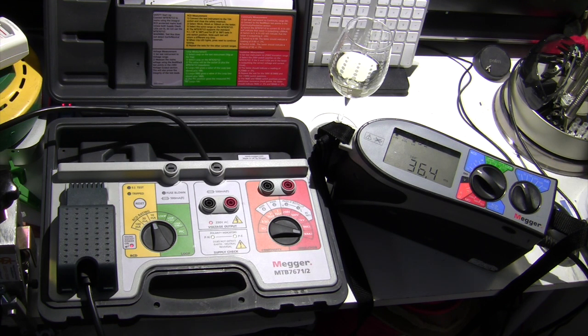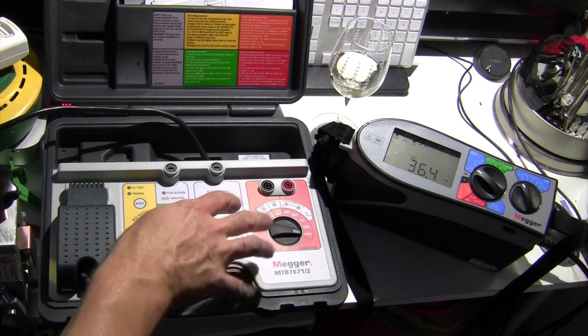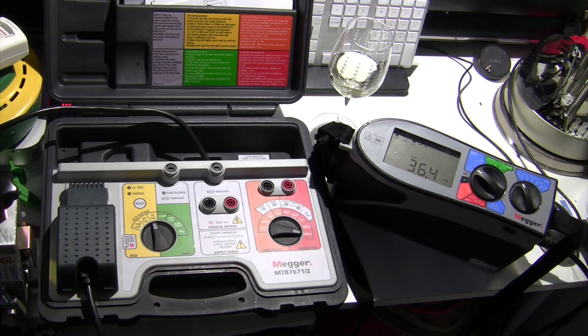Now again, the numbers change slightly here. The regulations state it should still be within 300 milliseconds, but the manufacturer's instructions for this say this test should be within 50 milliseconds, so it's slightly longer, but we need to see a result under 50 in order for it to be a pass. And if I press the button here, we'll see what it comes back with. 46.4, so super, that's passed.